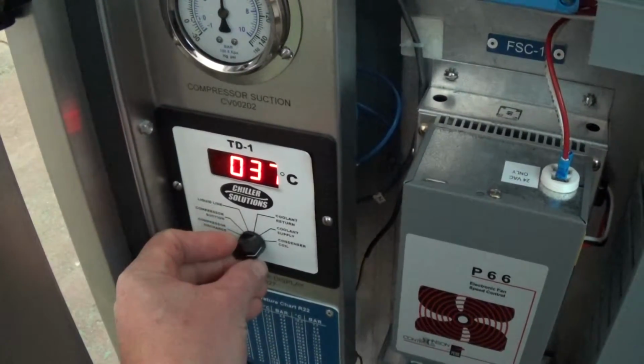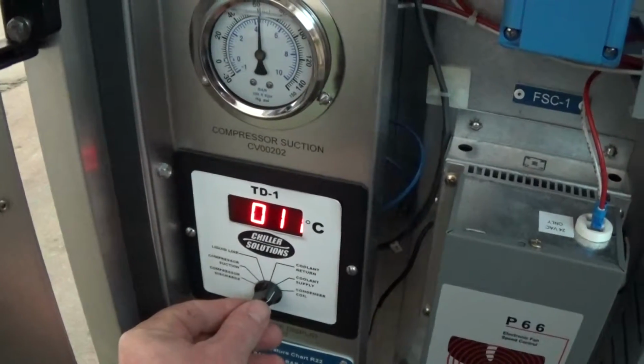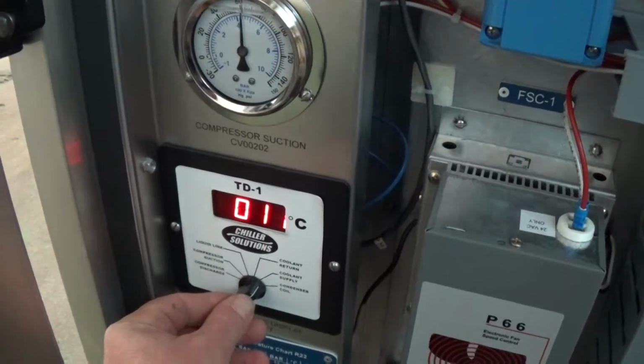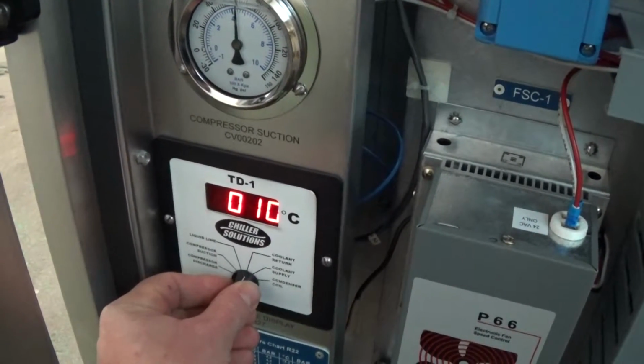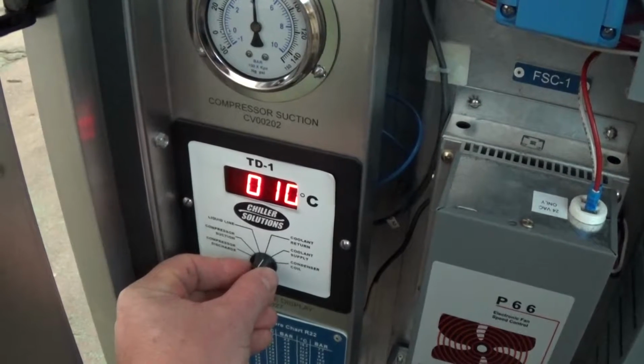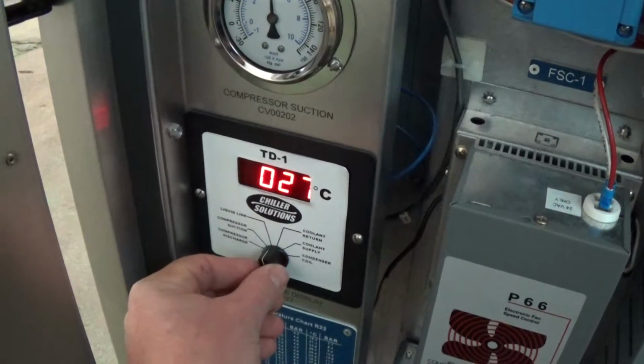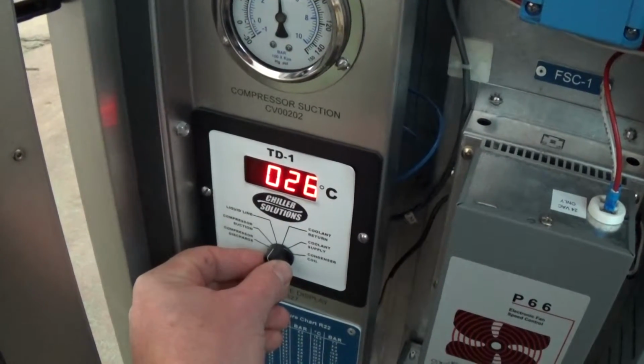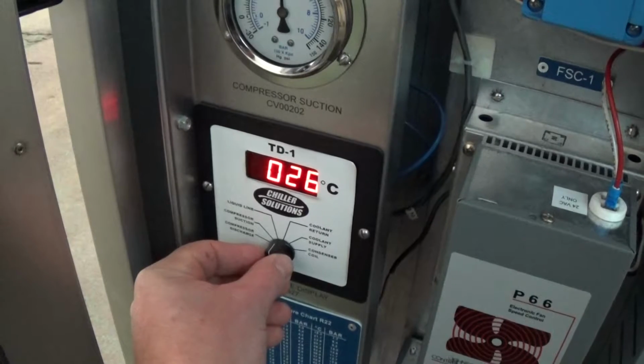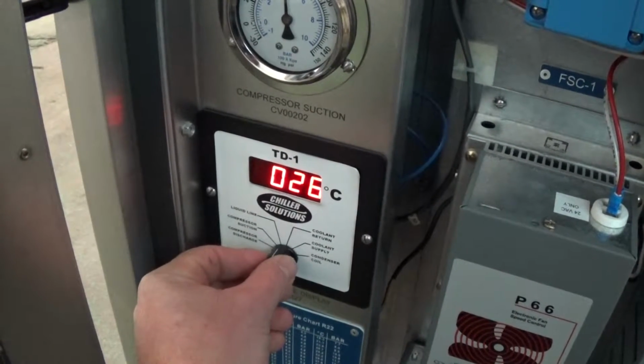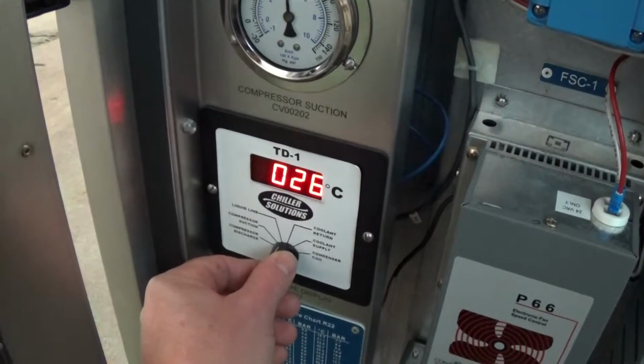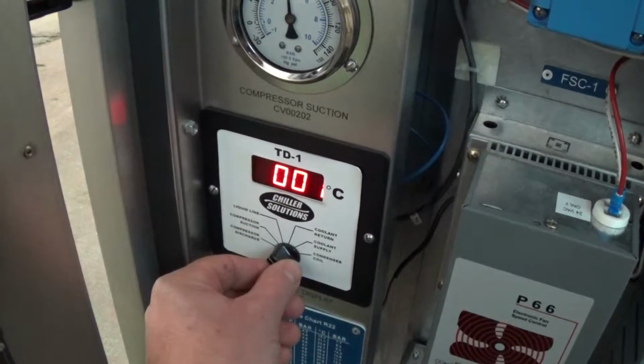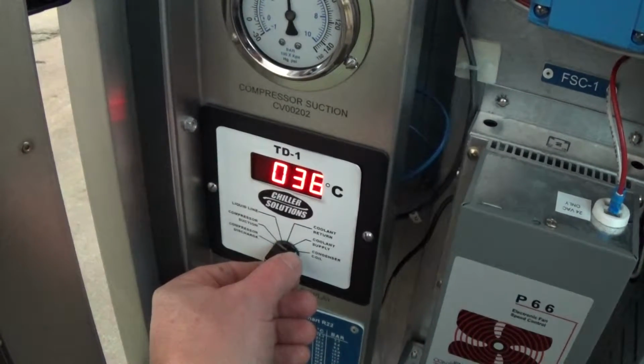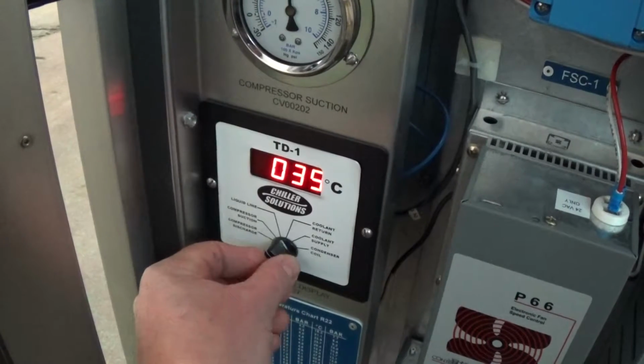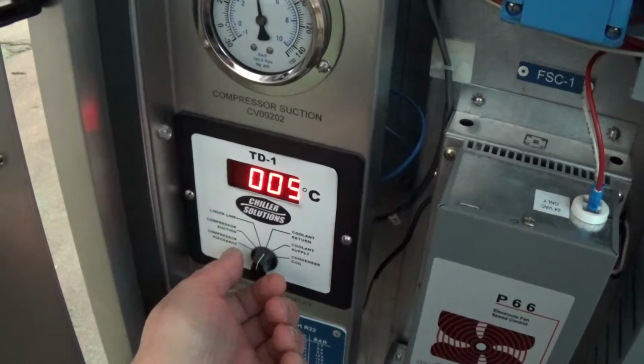Now that we started to chill, you can see we have condenser coil temperature, coolant supply, so that means that's a sensor that's sensing the output. We're down to 11 C already. Coolant return, 10 C. We really don't have a load on this, we're just cooling the tank, so that should be about the same. The liquid line, that's basically what's coming out of your condenser coil. So the refrigerant's going into the condenser, and that should come out a little bit cooler than what's going into it. Then you have the compressor suction temperature, in this case 1 degrees C, okay, and the compressor discharge temperature 38 degrees C right now, while we're cooling at a glycol temperature of about 9 degrees C.